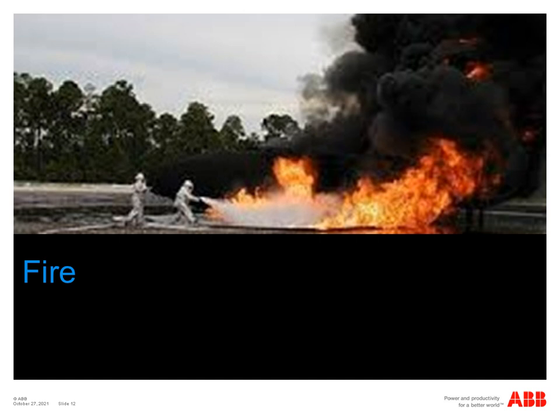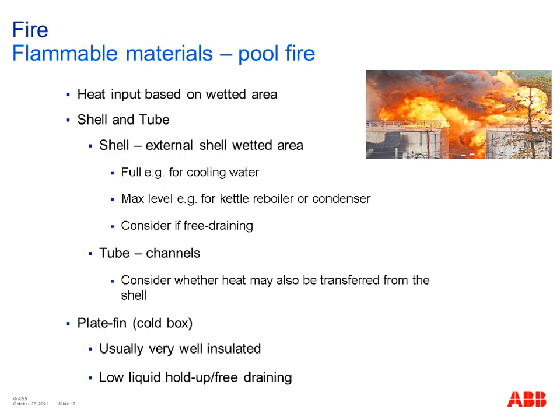So let's move on to fire. Fire cases are normally fairly straightforward. The heat input from a fire is based on the wetted surface area for the vessel, and this applies to any sort of process equipment. So in a heat exchanger, you'll be thinking about the wetted surface area for the shell. That's the surface area internal to the shell that's going to have liquid there that may be heated from the fire that's external to the shell. So then you've got this energy transfer from the fire into that liquid, and then it will obviously increase its energy, and it may boil.